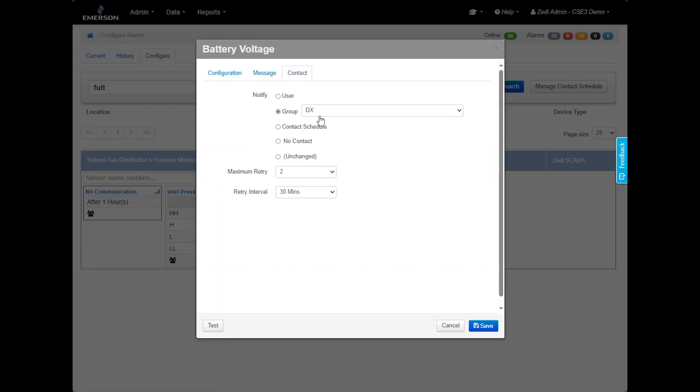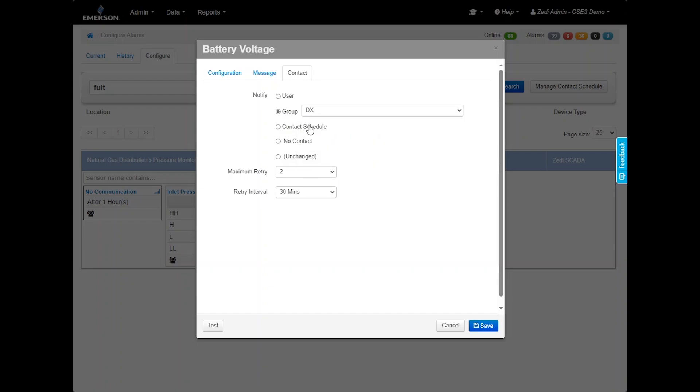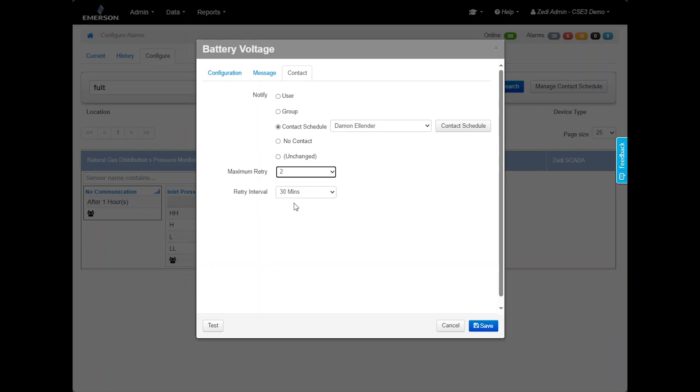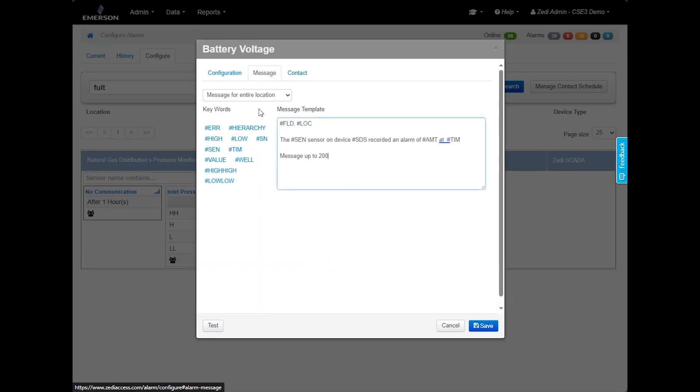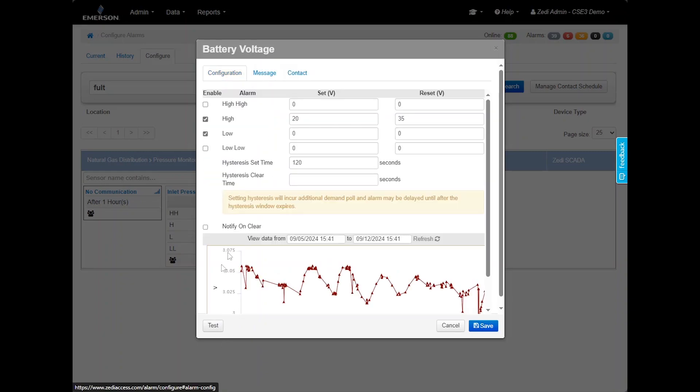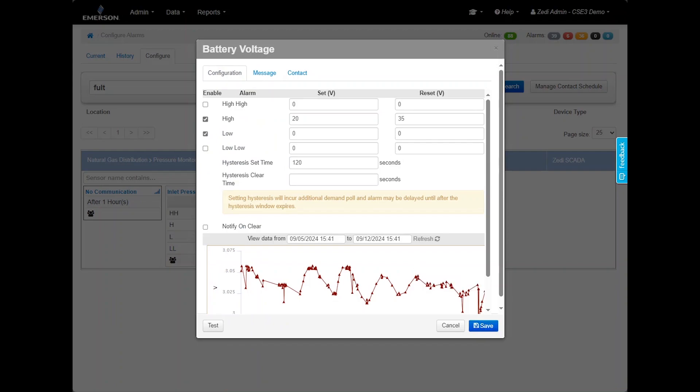The Contacts tab allows you to manage who receives alarm notifications. You can select individual users, groups of users or create a contact schedule. You can configure the maximum amount of retries by setting the number of times the alarm notification will be re-sent if not acknowledged. Set retry interval by defining the time between each retry. For example, if you set two retries with a 30 minute interval, the system will send out two notifications every 30 minutes if the alarm persists, ensuring that everyone is notified. Additionally, each tab includes an alarm test button in the bottom left corner of the screen. Click this button at any time to test the system and confirm that the correct individuals are receiving the alarm.